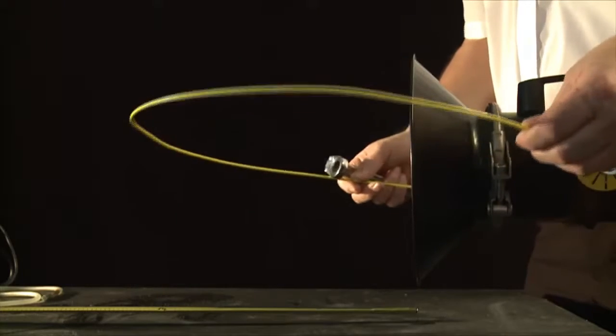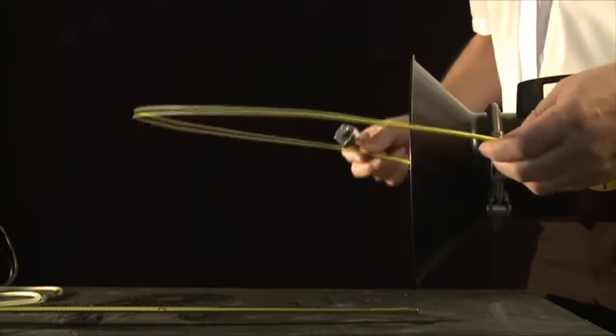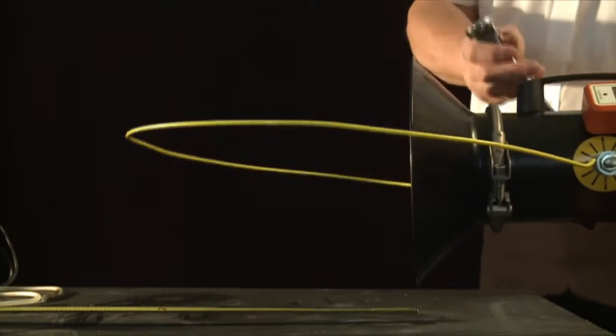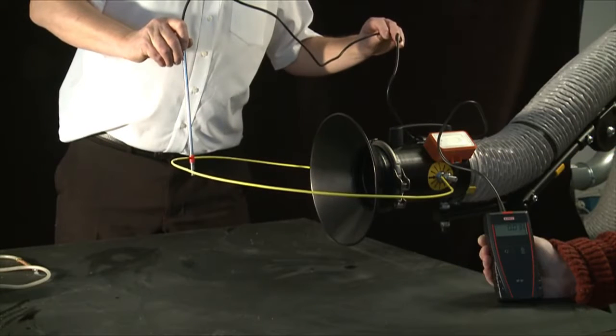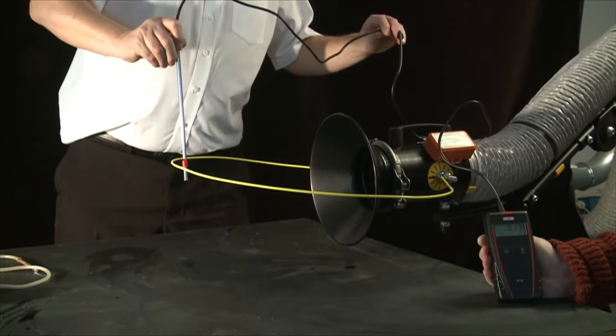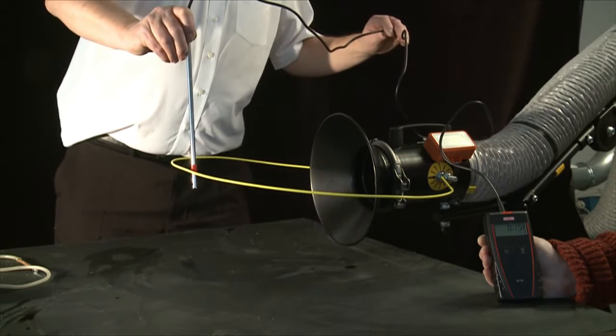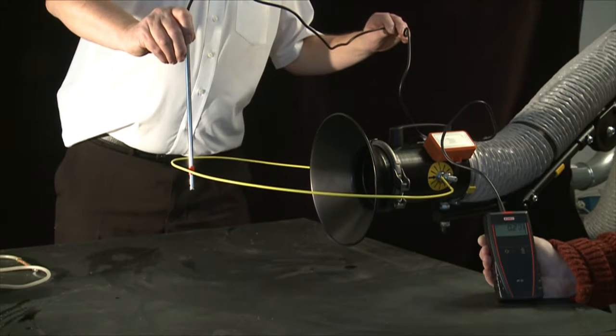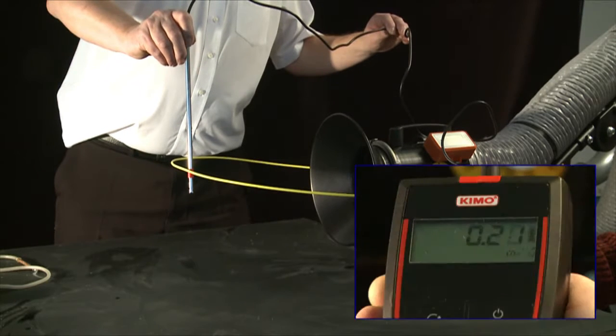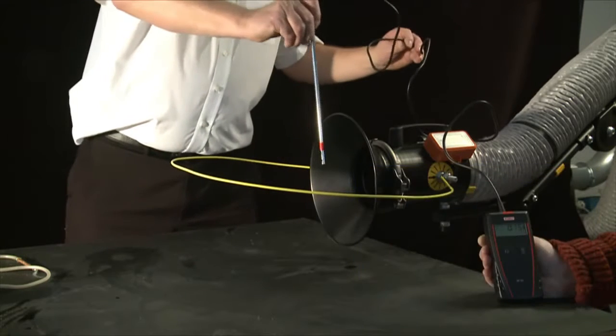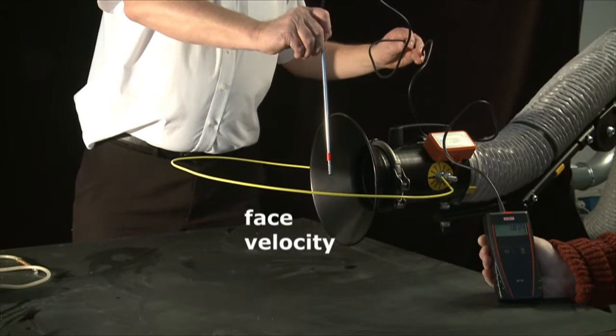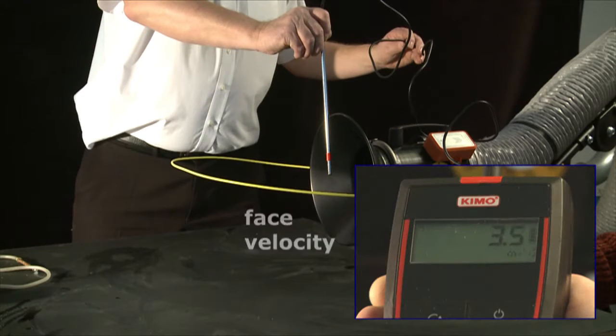For this demonstration, a yellow wire loop is fixed to the hood to represent the shape of the capture zone for this process. An anemometer is used to measure air velocity at the edge of the capture zone. In this example, the velocity at the edge is around 0.2 meters per second, and this is known as the capture velocity for the process. The velocity at the face of the hood is 3.5 meters per second.